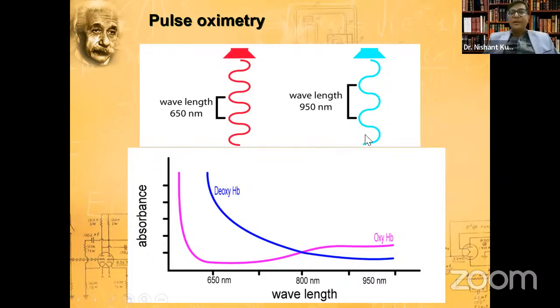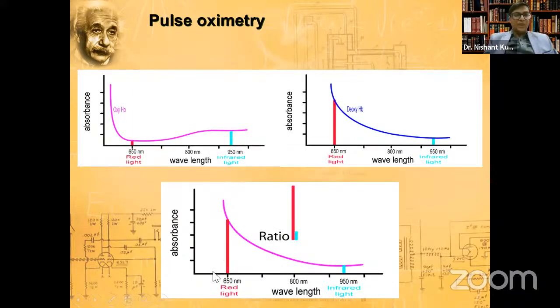Infrared light is normally not visible to the naked eye. The wavelength of red light is 650 nanometers, and for infrared light, it is 950 nanometers. We have the deoxyhemoglobin curve and the oxyhemoglobin curve. Now, if you see, the absorbance at different levels is different. How? The absorbance for oxyhemoglobin is more for infrared light, and for deoxyhemoglobin, it is more for red light.